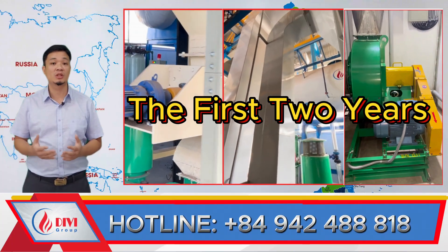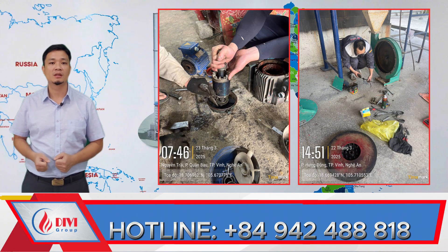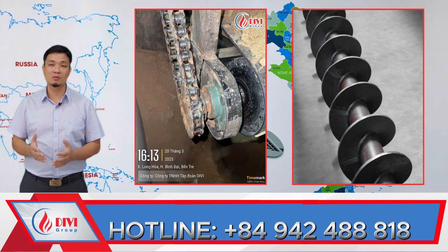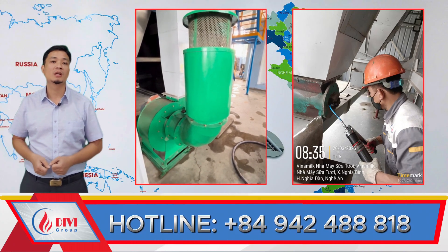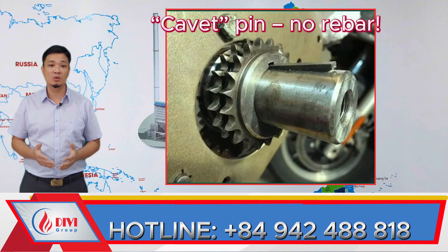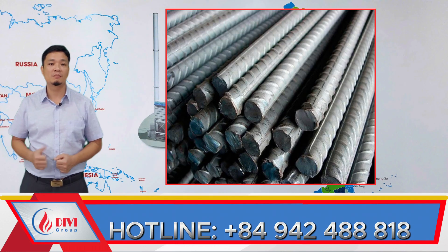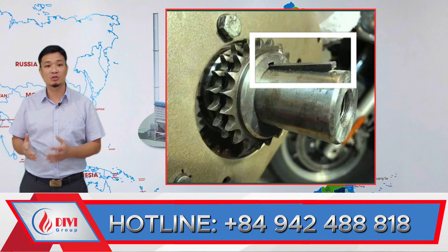Especially after year three, you should check motor bearings, change gearbox oil, repaint insulation, and lubricate moving parts on schedule. Make sure to grease all moving components like sprockets, chains, and shafts — without proper lubrication, dust and moisture can cause corrosion and wear, eventually leading to breakdowns. Also pay attention to the coupler pin (or cavette, as it's often called in southern Vietnam) that connects the motor to pulleys or gears. Some operators use construction rebar like Phi-6 or Phi-10 as a shortcut, but these break easily — always use the right hardened material.